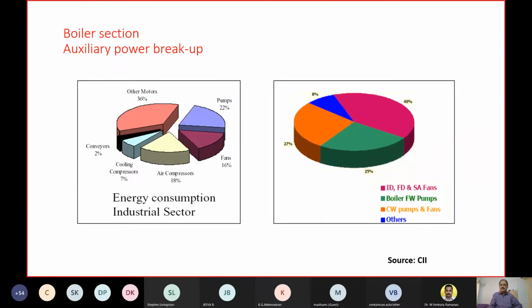If you compare, once again, a typical industry application vis-a-vis the auxiliary power consumption in a thermal power plant, you will notice that ID, FD, and SA fans contribute 40% of the total power. Boiler feed water pumps will be 25%. And condensate extraction pumps and fans will be 27%. Others will be 8%. These others would be BOPs like ash handling, coal handling, conveyors, crushers, and so on. So this is how the total auxiliary power consumption is shared.